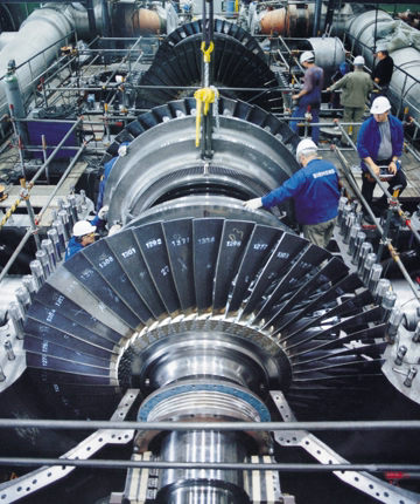To the more technical: how should the generator start? Some turbines act like a motor to bring themselves up to speed, in which case they need an appropriate starting circuit. What is the mechanical speed of operation for the turbine, and consequently what is the number of poles required? What type of generator is suitable, synchronous or asynchronous, and what type of rotor: squirrel cage rotor, wound rotor, salient pole rotor or cylindrical rotor?